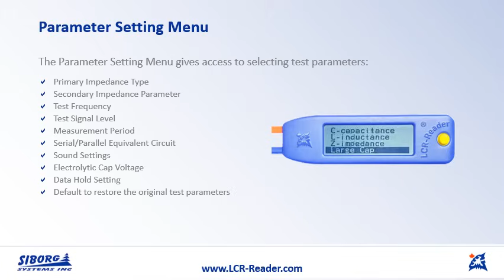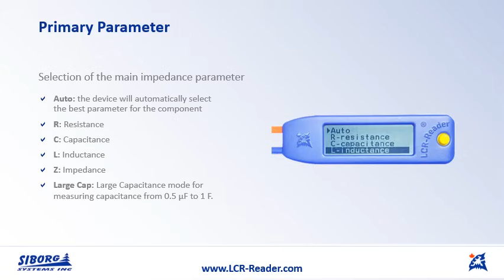Primary parameter. Selection of the main impedance parameter, auto. Device will automatically select the best test parameter from R as a resistor, C as a capacitor, L as inductor, Z as impedance. Large cap is a special mode for measuring capacitance from 0.5 microfarad to 1 farad.